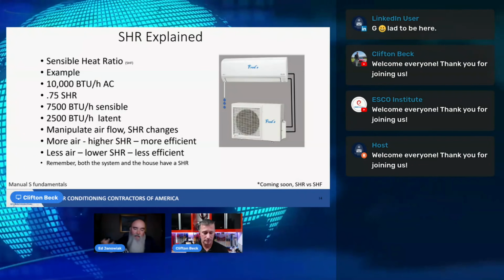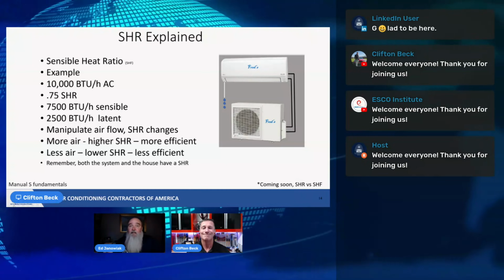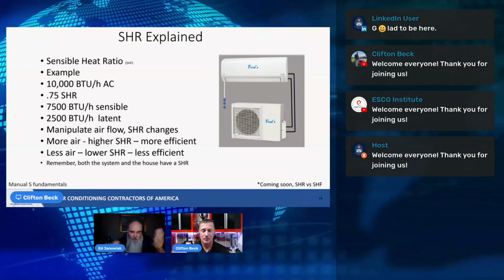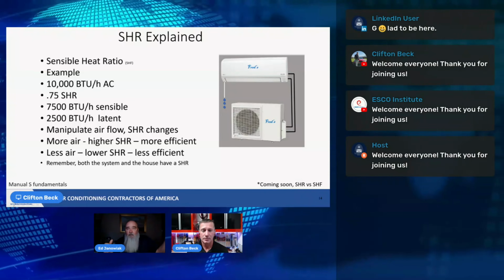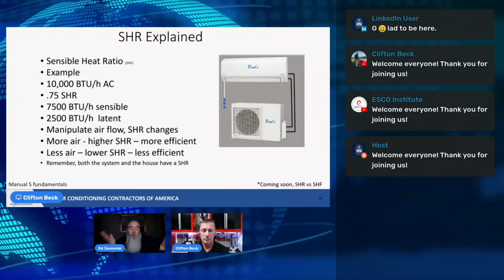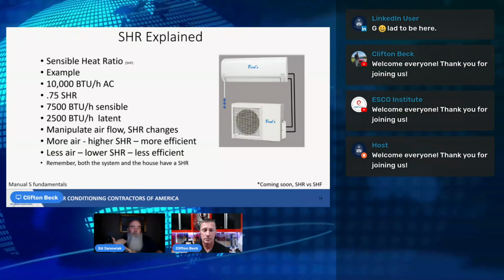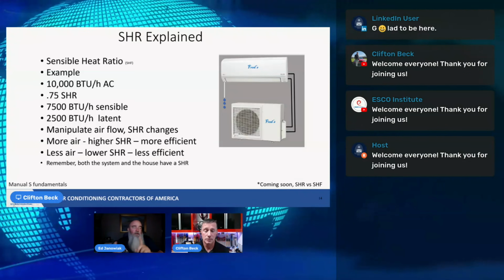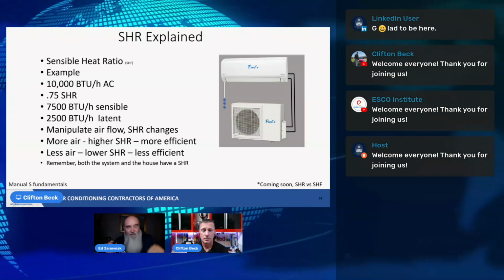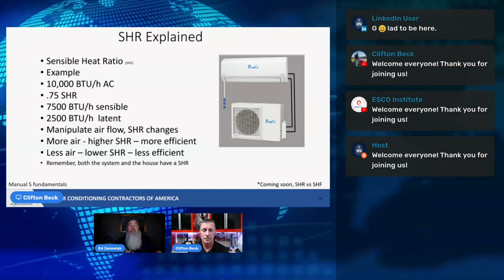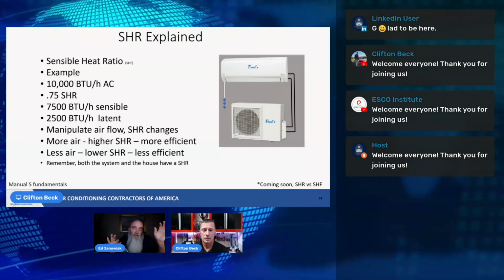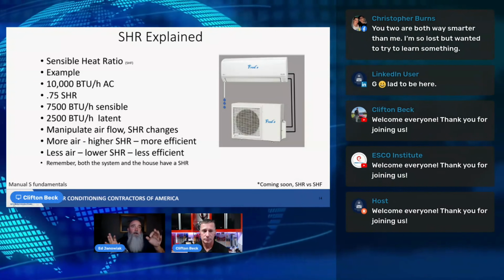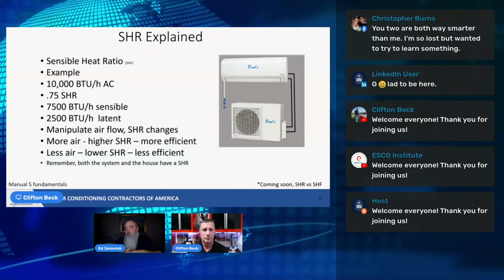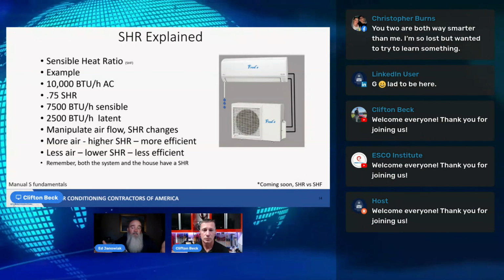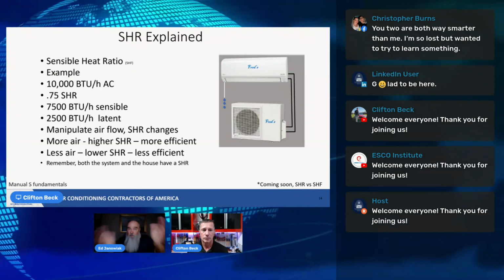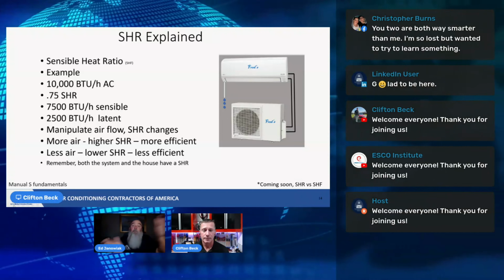That leads me right into Manual S, which is in the current state of being updated. Although it does address the two-stage and VRV equipment with the higher tolerance for acceptable wiggle room above the gain on the structure, right? We got a whole new set of rules coming out. If you're in a dry climate, and I'm paraphrasing, but it says do whatever you want. If you can create a dry climate condition, which essentially is if you have VRV equipment and the manufacturer publishes its very low speed operating performance, then as long as we can guarantee our latent removal, you can put a bigger piece of equipment in.